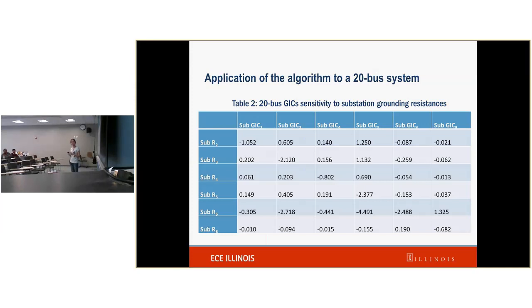As an example, let's look at the sensitivity of GIC 4 to R4. The value is minus 0.802, which means that if the difference between the estimated value and the real value is 0.01 ohm, then the difference between the calculated GIC and the real GIC is about 0.8%.